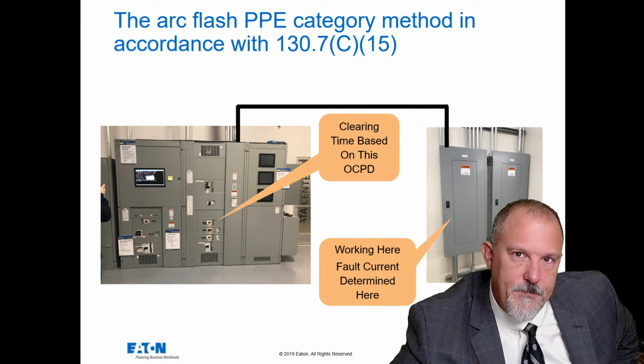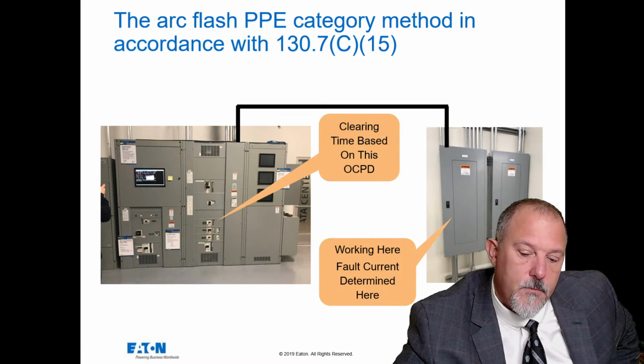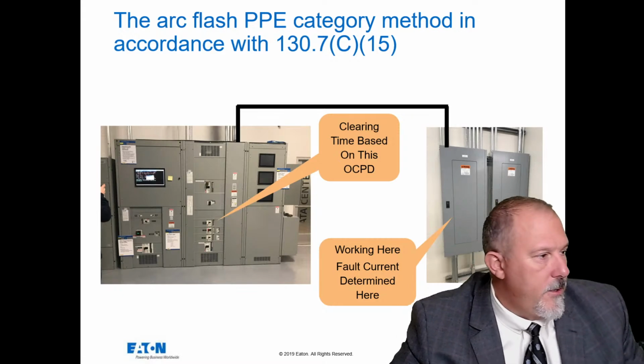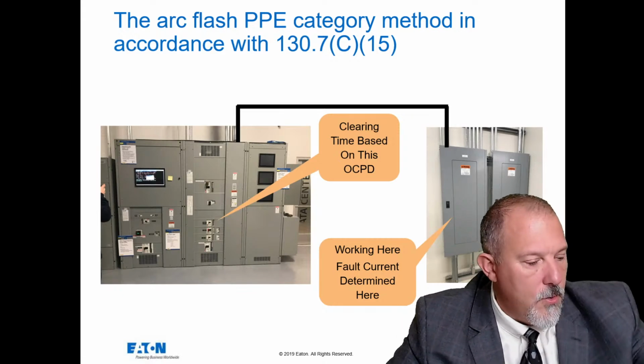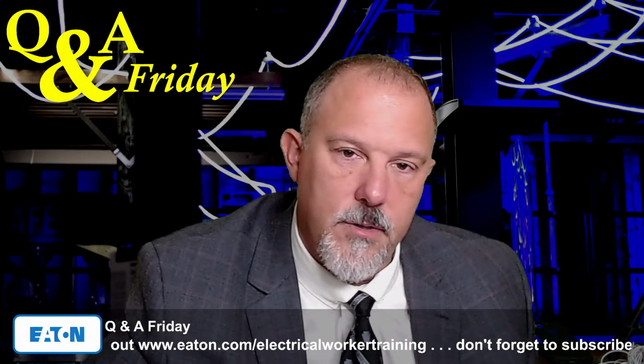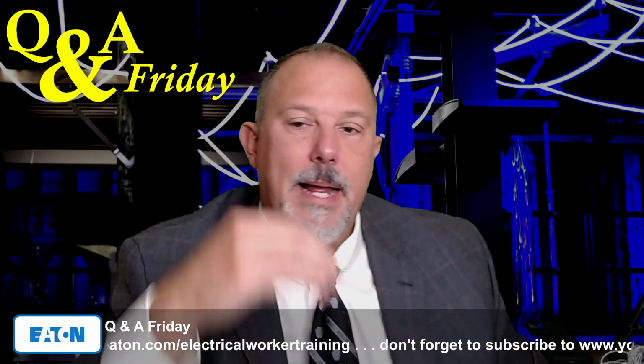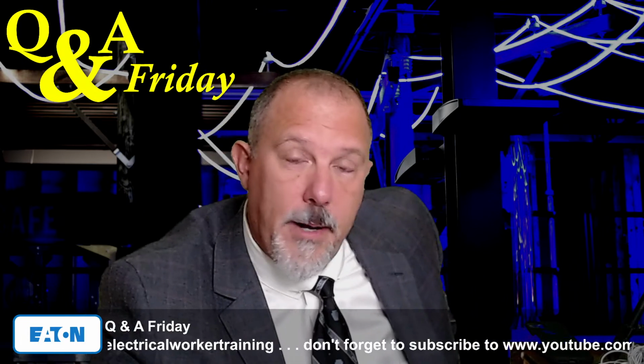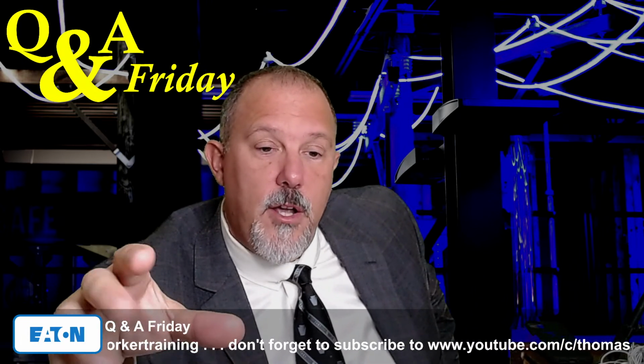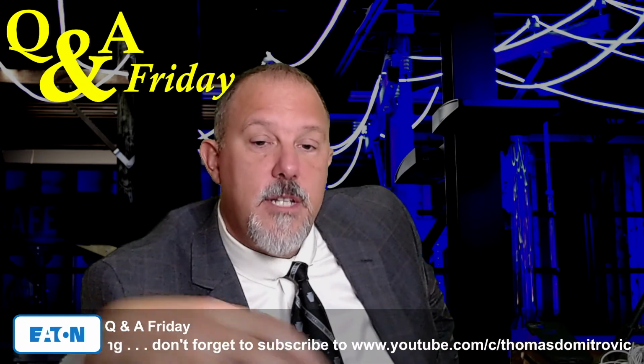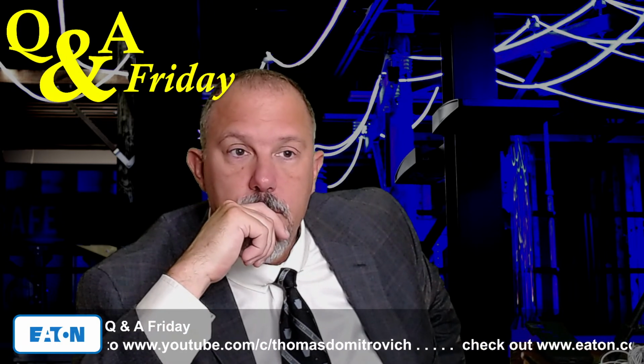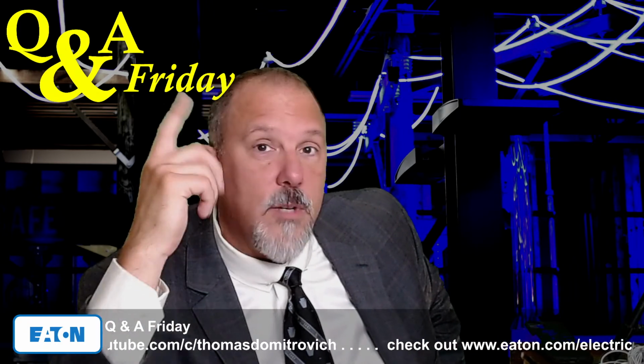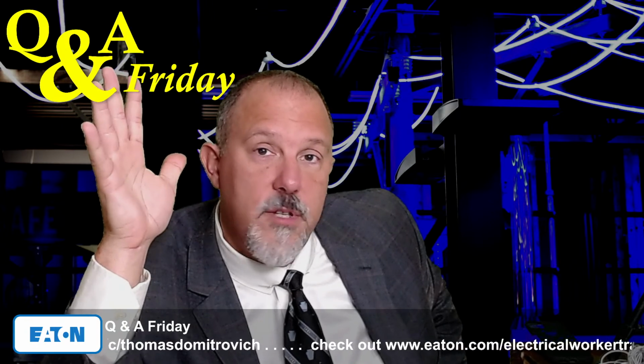You see what I'm saying? So JW, there's no real easy answer to your question, but I can say it has nothing to do with the series ratings. The arc reduction maintenance switch doesn't have any effect on a downstream series rated breaker. None whatsoever. It's a different goal, different task.